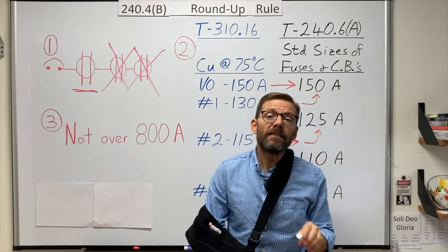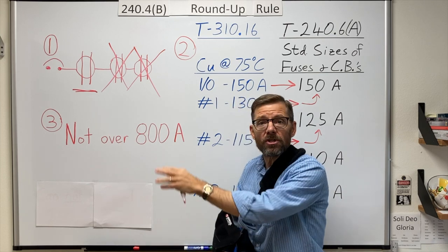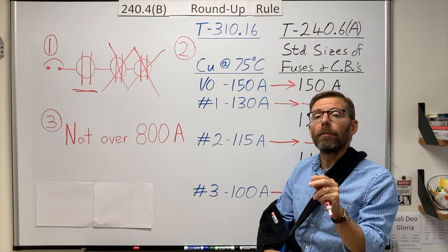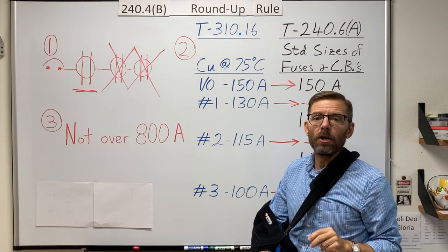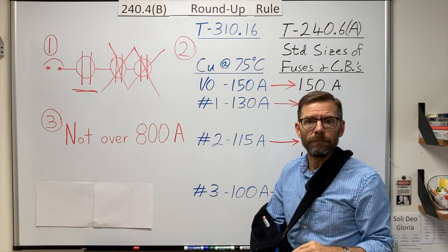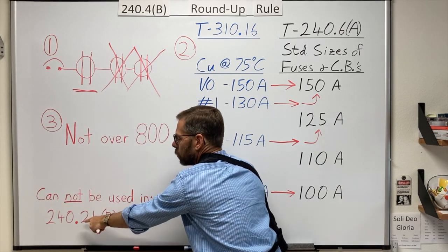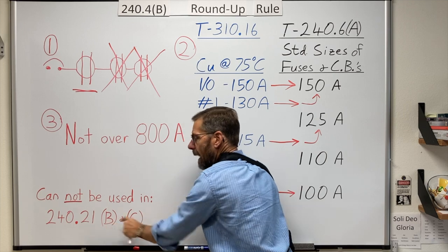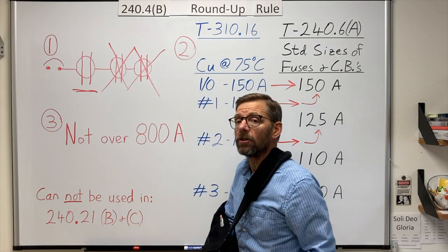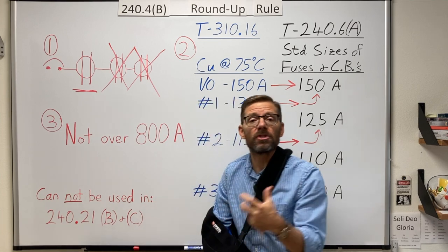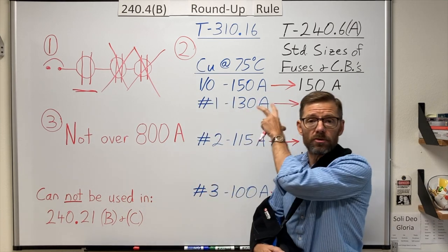So as an additional remark, even though this is a general use permissive rule, there are a couple of specific circumstances where we cannot use this rule. If I look right here, 240.21B for tap conductors, I cannot use this rule. And C for transformer secondaries, I'm not allowed to use this rule. I can use this rule for transformer primary conductors, but just not on the secondary side.